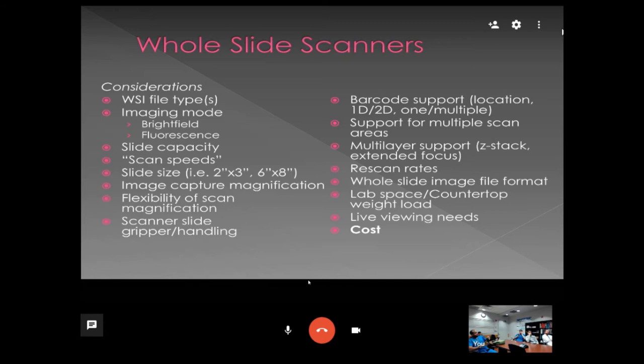What type of slide size does the department need? Are you just doing traditional slides, or do you need to do whole mounts, for instance, for prostates? Different whole slide scanners can accommodate different slide sizes. What image capture magnifications do you need? Different whole slide scanners can have 20x, 40x, or 63x objectives inside them, and depending on the objective, you get different resolutions.